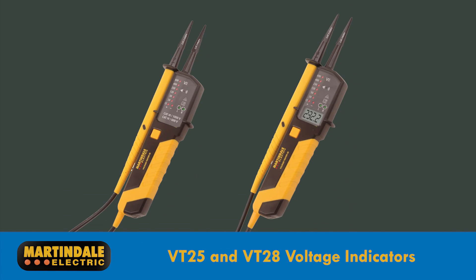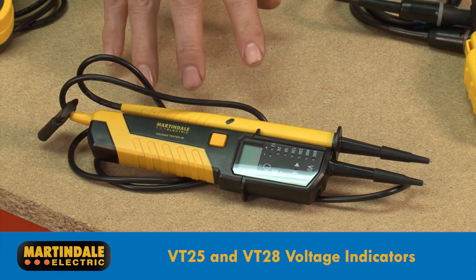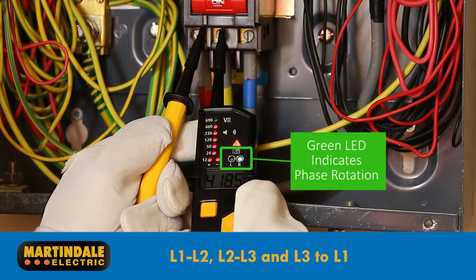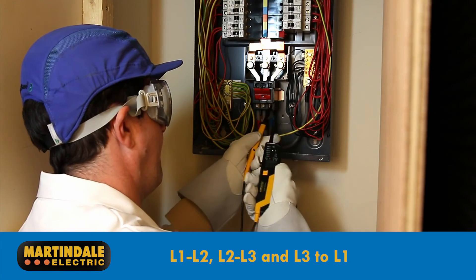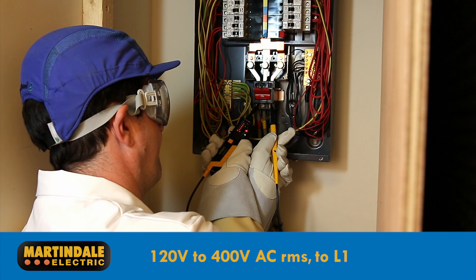Another solution are the VT25 and VT28 voltage indicators. Because these are two-pole testers, the phase-to-phase voltage and direction of rotation will have to be taken between each phase in turn: L1 to L2, L2 to L3, and then L3 to L1. They operate between 120 and 400 volts AC RMS for 50 to 60 Hz supplies.